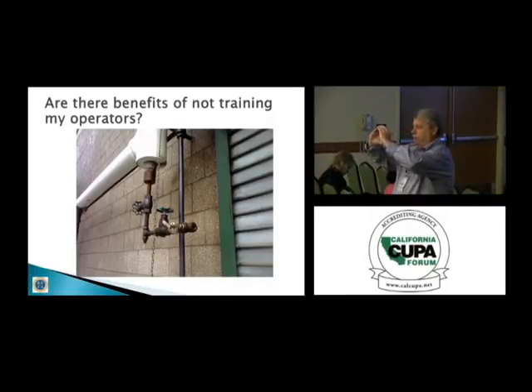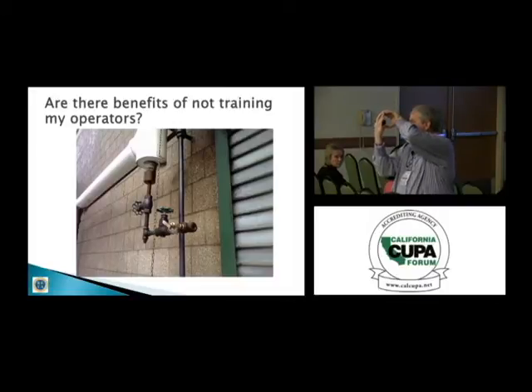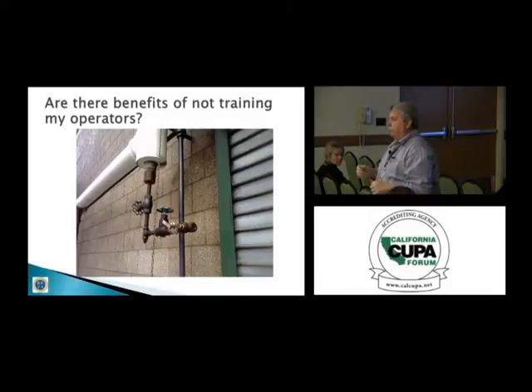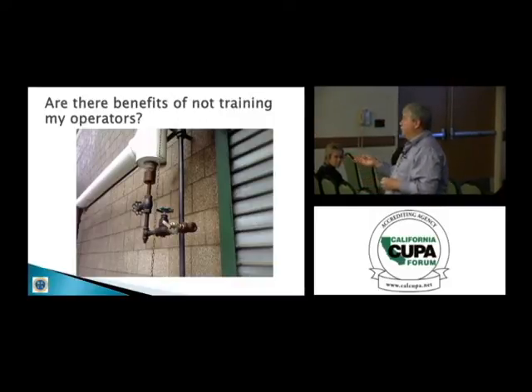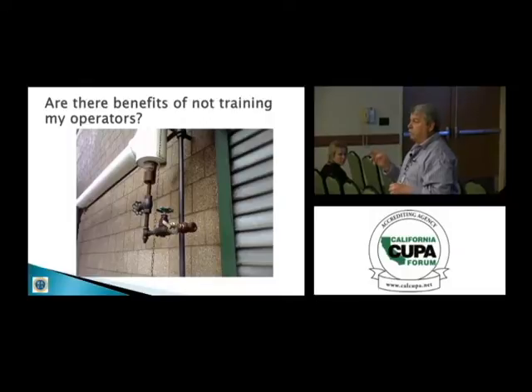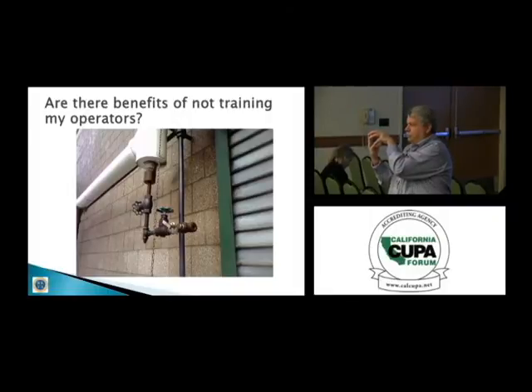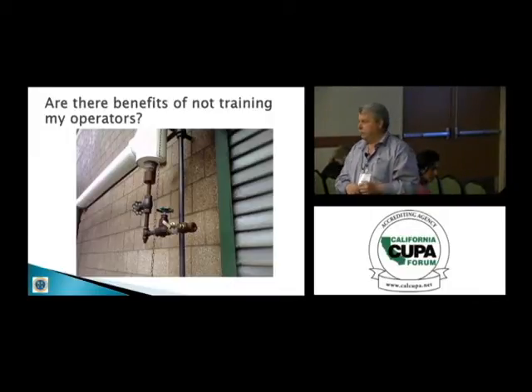In a ball valve, you've got a cross section that is basically the size of the pipe, and when you turn that, you've trapped what was in it, and now it's got nowhere to go. The appropriate ball valves for oil draining have a hole drilled through one side that goes back to the system, so that whatever you trap in here, when it warms up, can make its way back to the system. So if your facility is proactive and has these self-closing valves, ask them if they know that they are vented, so that you don't have this potential breakdown because of the warming up. Again, we've got an example of hydrostatic damage that can happen.